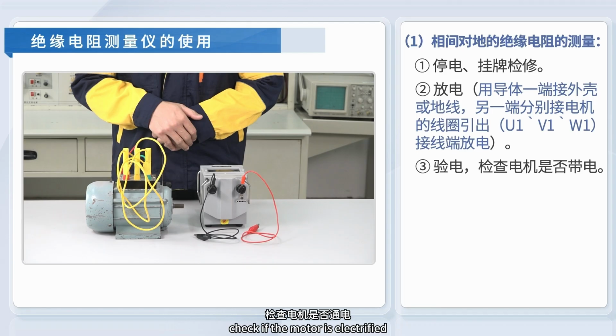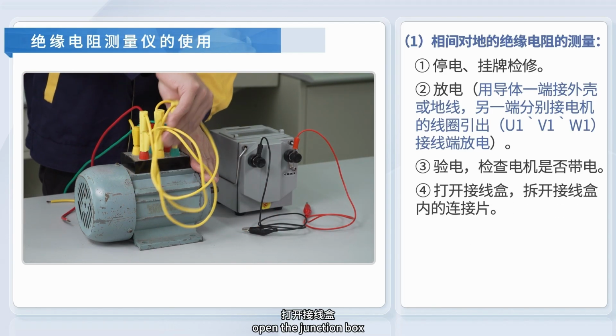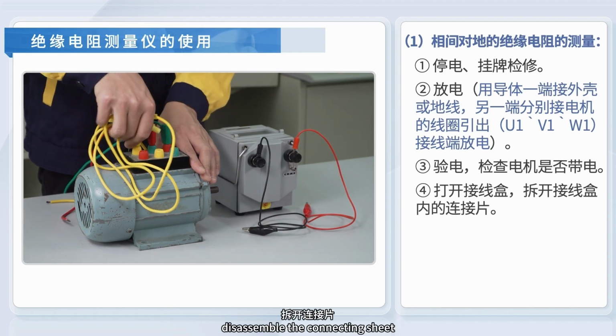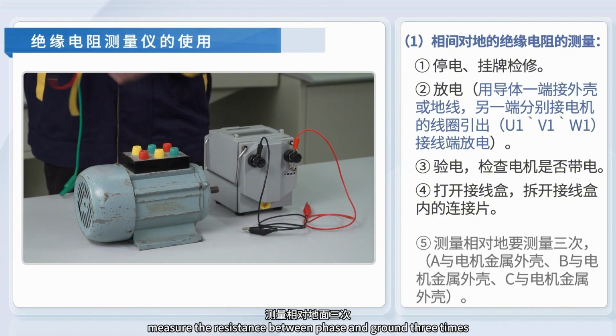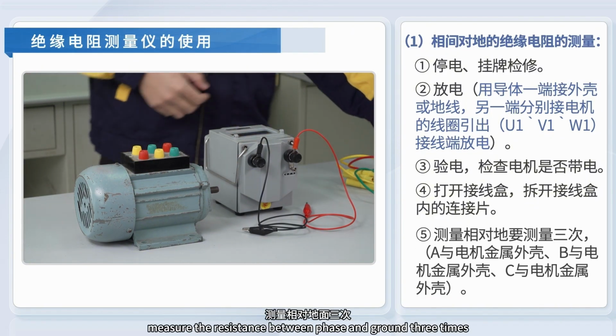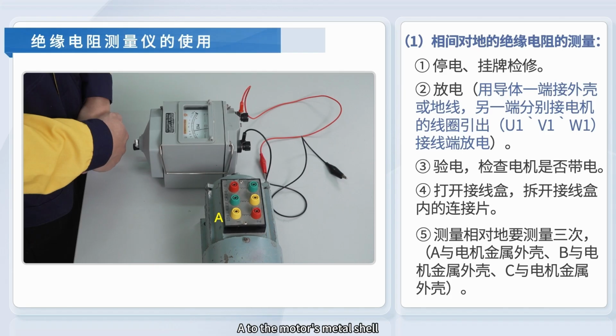Check if the motor is electrified. Open the junction box. Disassemble the connecting sheet inside the junction box. Measure the resistance between phase and ground 3 times. A to the motor's metal shell. B to the motor's metal shell. C to the motor's metal shell.